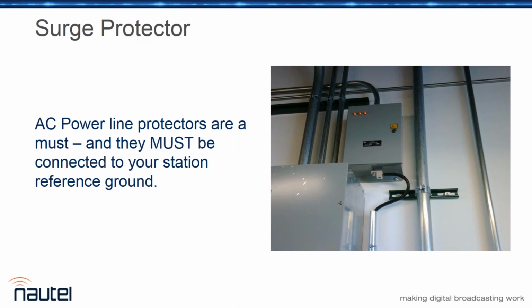And one other thing, and you'll see that on this picture. Number one, your surge protector needs to have a ground connection. Number two, don't run that ground through a conduit. Conduit's ferrous material. It's just like putting a giant ferrite over a piece of wire and creating a choke. So you've just added impedance to your lightning path. And this is the path we want the lightning energy to go, not one where we're trying to prevent it.